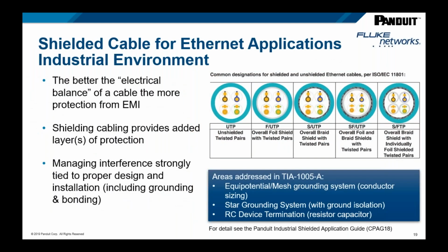Looking at another part of M.I.C.E., the E factor, or EMI. This is probably the most consequential, maybe the most important area in terms of M.I.C.E. Problems in this area can cause intermittent performance in the network, which is one of the hardest things to trace and correct. Things to consider around shielding and noise: first, the source of the noise, determining where that noise is coming from. Is it within the cable? Is it outside the cable? How is it being brought to the control panel, for example? And then the design of the grounding and bonding system.